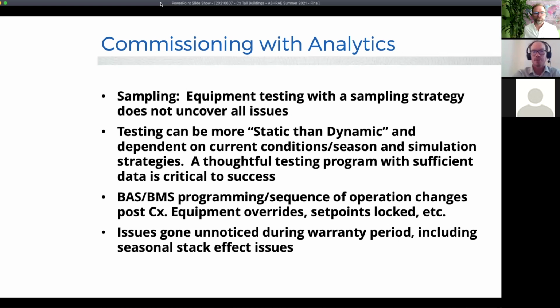The other thing that bugs me about the traditional commissioning process is that we look at something at a certain point in time, and hopefully we're allowed to test those systems at that given season, or at least their design season—seasonal testing. But that doesn't always happen, and it doesn't mean that's going to stay that way. So having something in your back pocket that's looking at this all the time clearly adds value, and we're going to prevent issues, keep folks more comfortable, and mitigate a bunch of those issues that happen with buildings with poor or severe stack effect.